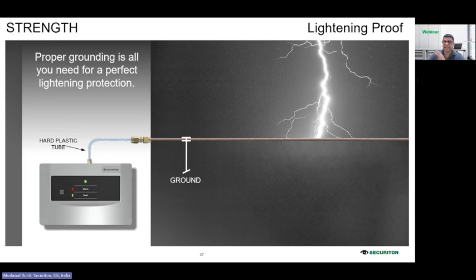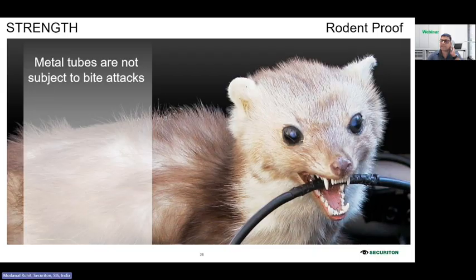Our product ADW535 is lightning proof because its air detection tube contains no field electronics. This design makes it immune to lightning, electromagnetic fields, and strong electrical disturbances. So you can use it in the outside area also, where there are conveyors carrying material inside your manufacturing area. There is no effect of lightning or of electrical disturbances. It is rodent proof if you are using a metal tube like copper or stainless steel tube, so you can easily install it for inside and outside applications.